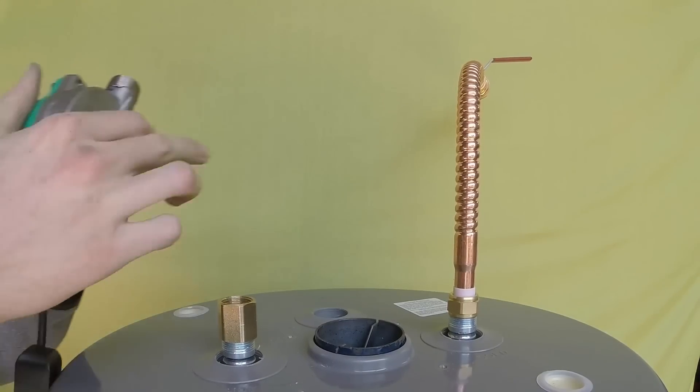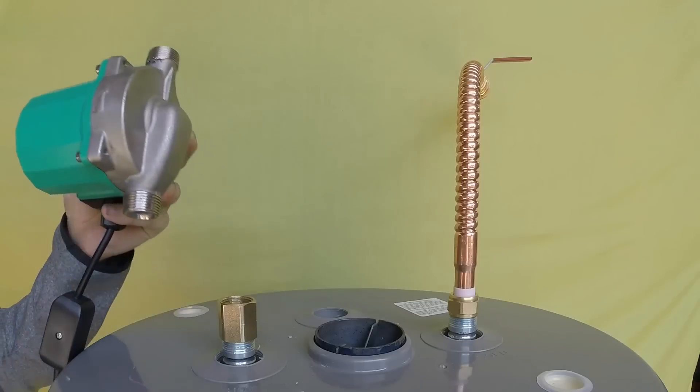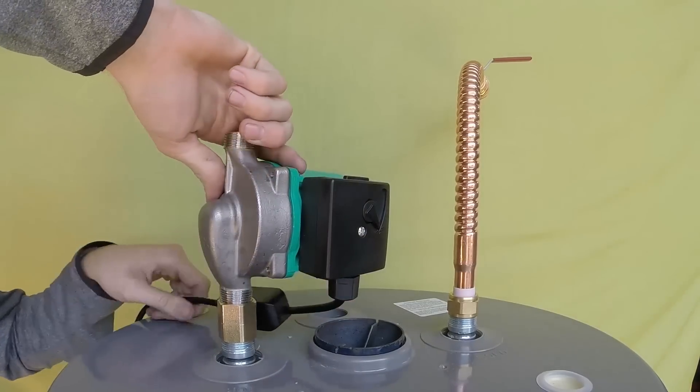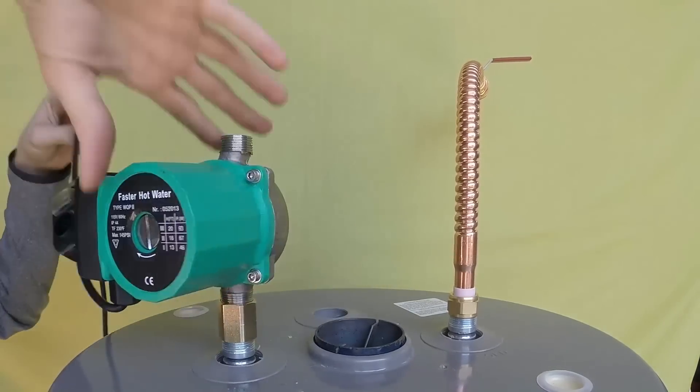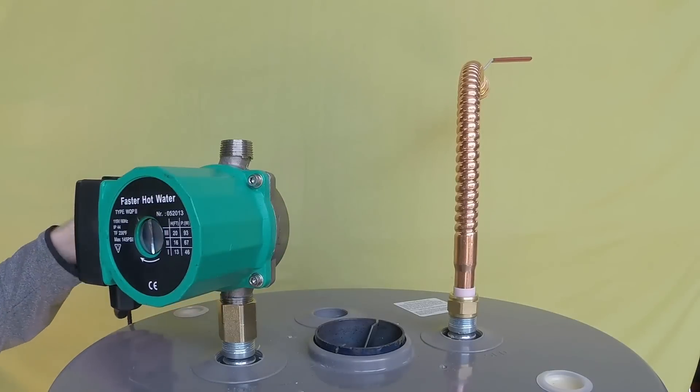Use Teflon and or pipe dope on the upstream side of the pump. Make sure the arrow on the silver part of the pump is pointing up in the direction of water flow. Screw the pump into the three quarter inch coupling until snug. Make sure all parts of the pump are clear of the vent.